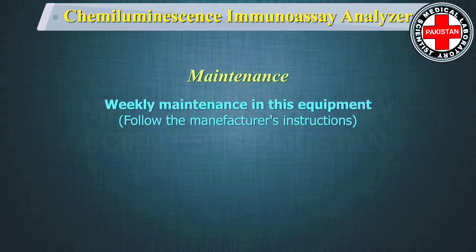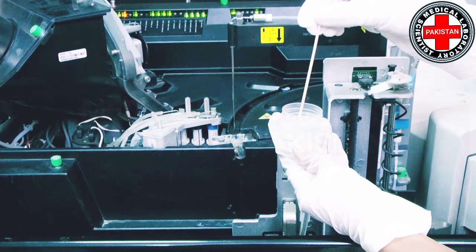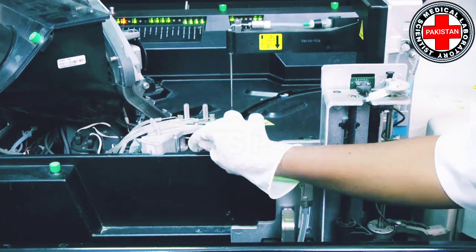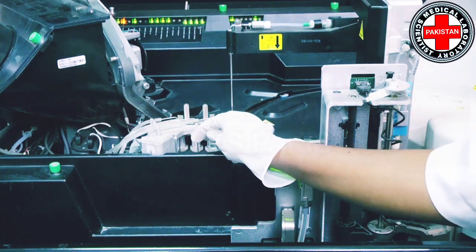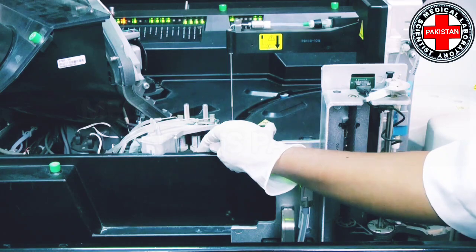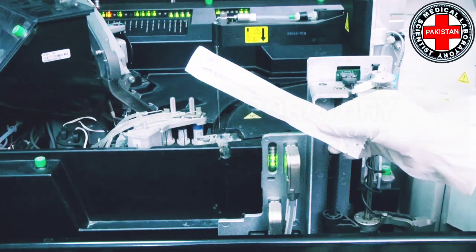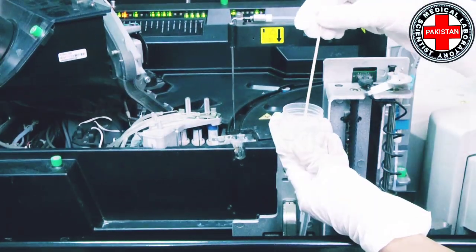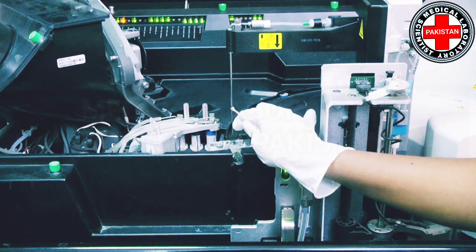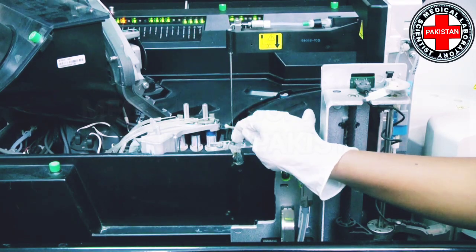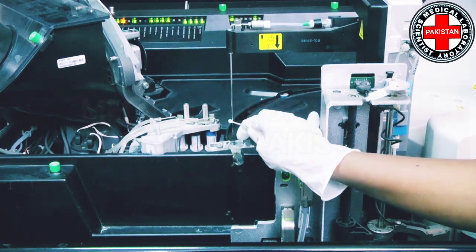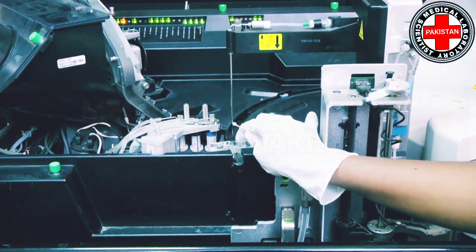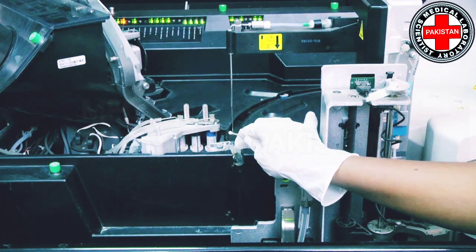Weekly maintenance: Clean the probes and surrounding areas with distilled water. Use a sterile swab dipped in distilled water and gently clean the outside of the probes, taking care not to bend or break them.